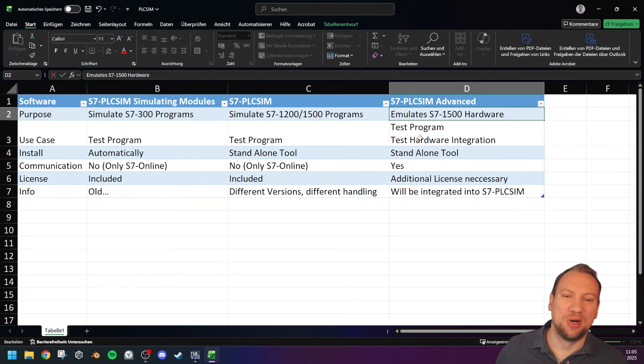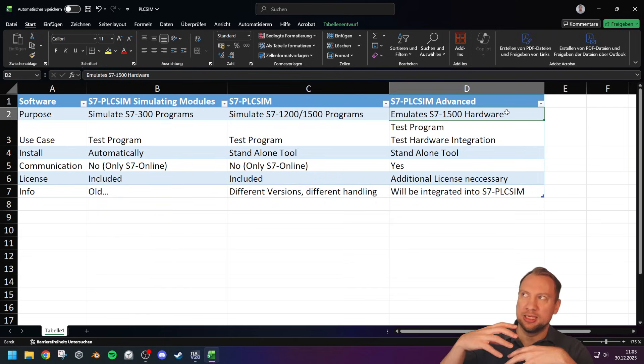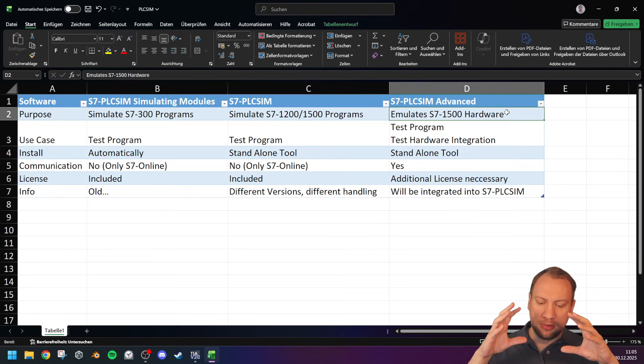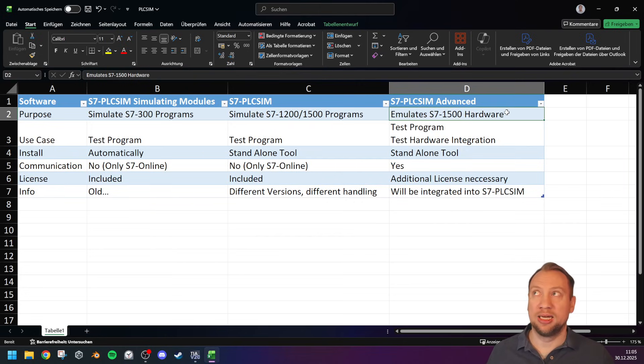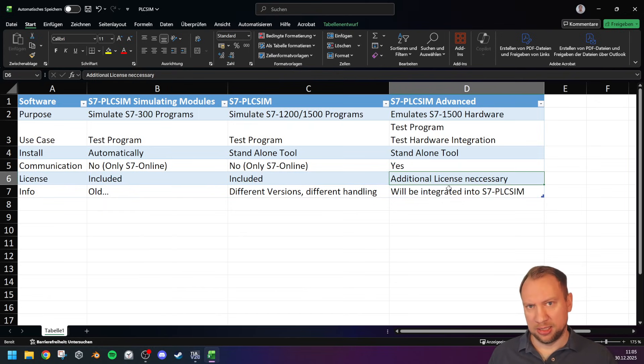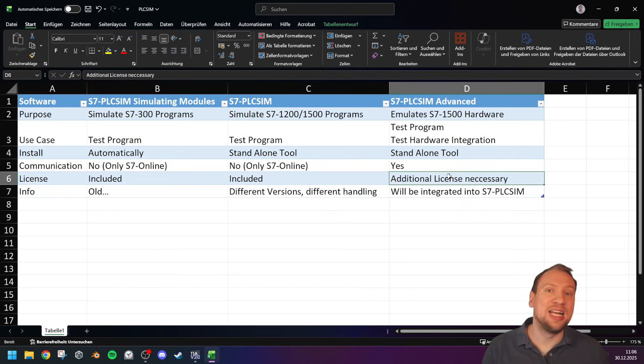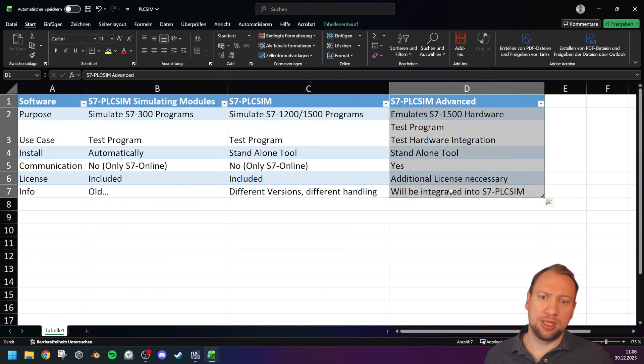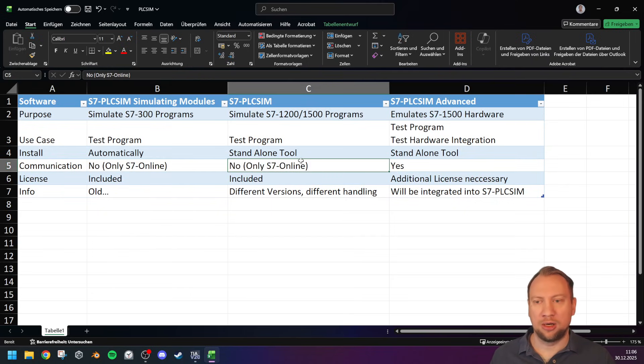However, there is sometimes the demand to have your project communicate to other devices — for example, to an HMI, a different PLC, a server, or an OPC server. This is where you don't really want to simulate your program anymore; your main purpose becomes to emulate your S7-1500 hardware. This is necessary because it will get a network interface with the correct timing and cycles. If you really need to do an integration test in hardware, you will actually need PLC SIM Advanced.